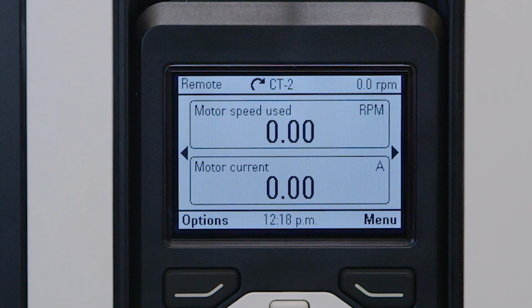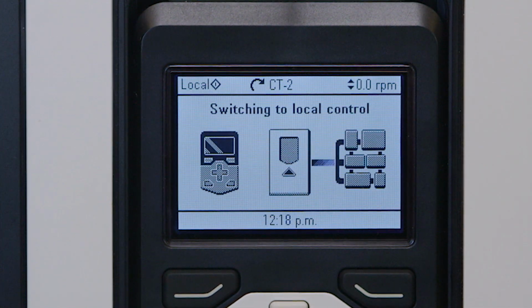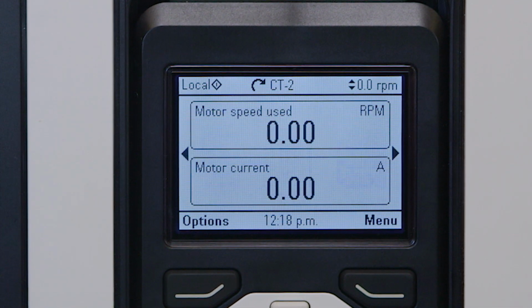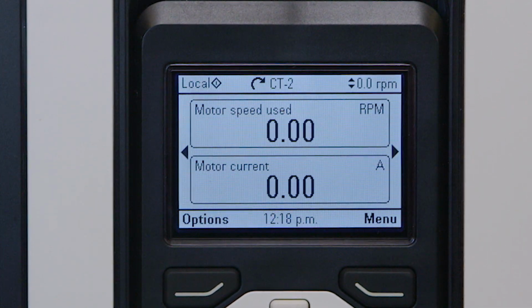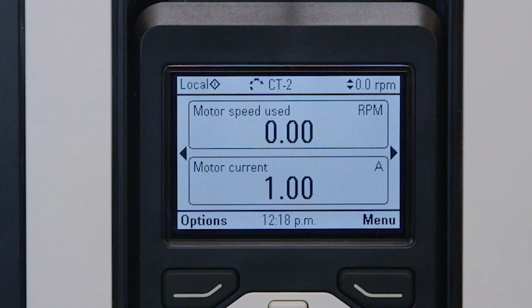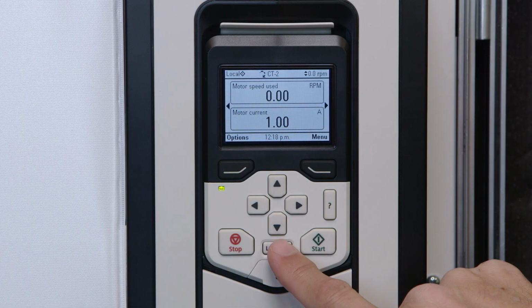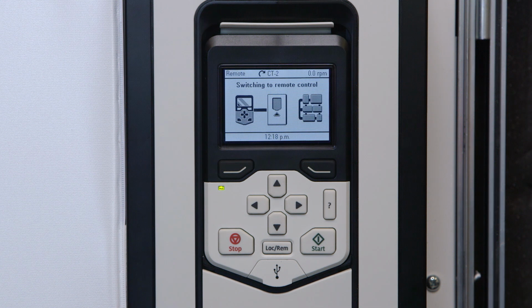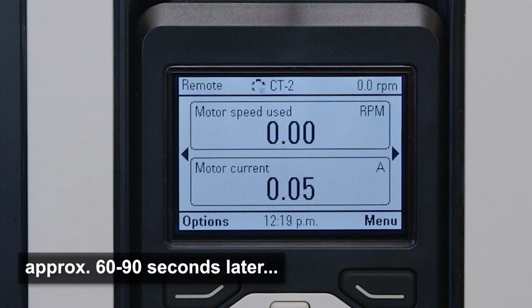To activate trickle current if there is no BMS, use the following procedure. Press the Loc Rem option on the display to switch to local mode. Press the green Start button and wait for the arrow to start rotating. Press the Loc Rem button to switch to remote. Wait for the trickle current delay time and then ensure trickle current activates.